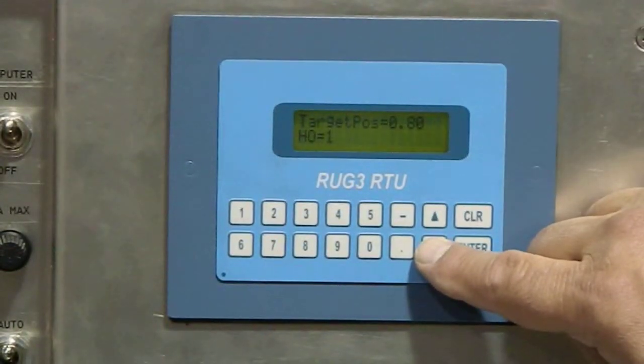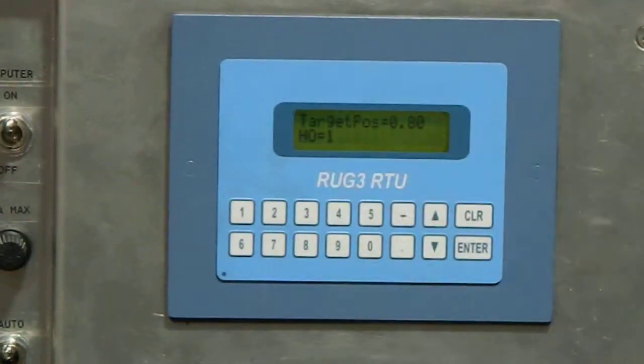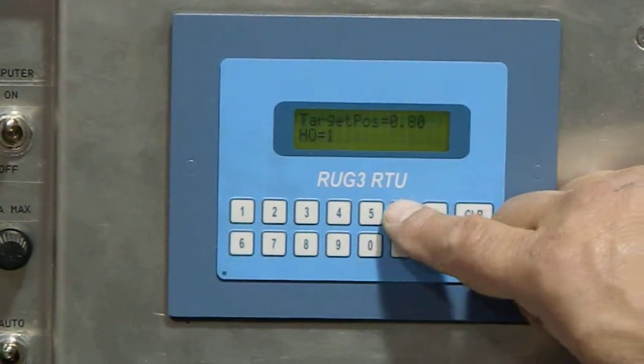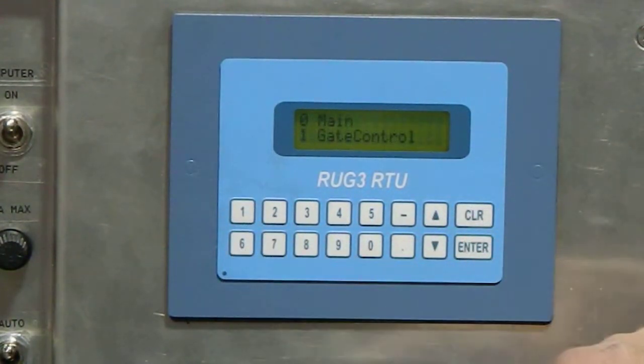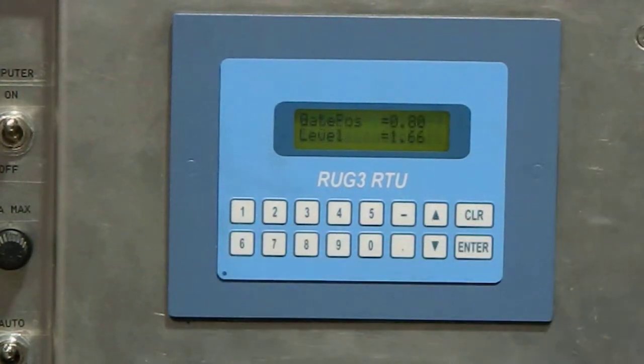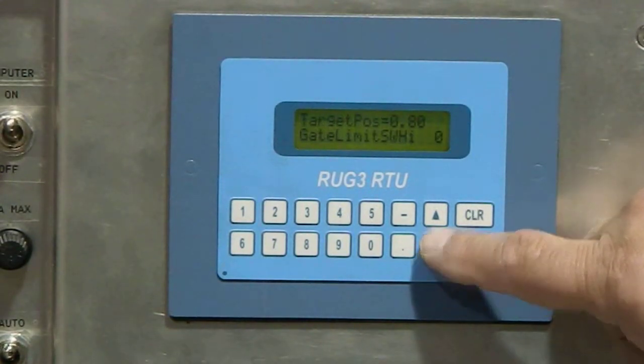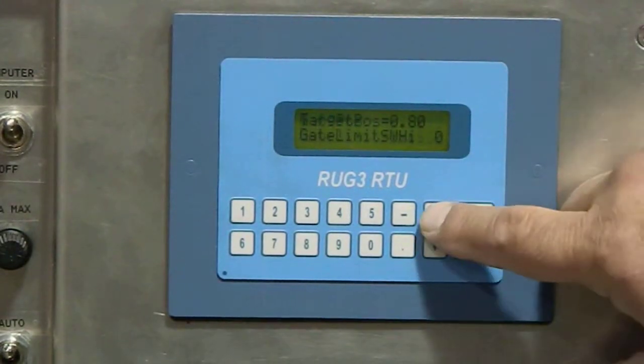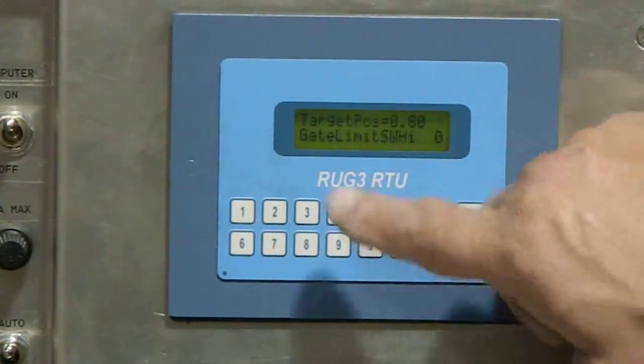The first screen, once again, gives you the time and the date, the address of the system, and local data: gate position, the level sensor, and the target. HO means, 1 means that it's in the automatic mode. It's enabled. Minus 1 gets you to the screen control system. We go 1, we go to the gate position, gate control screen again. Here's our target, our level, and our target for the position that we want to set. So in other words, that's the gate position, that's the target.